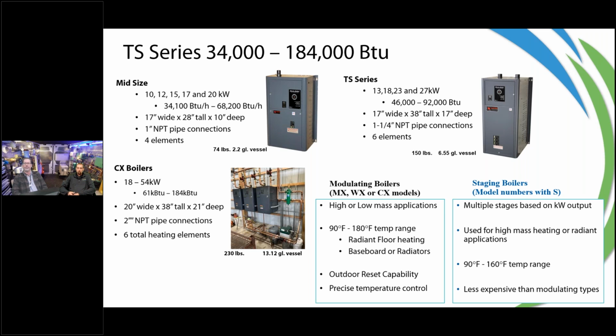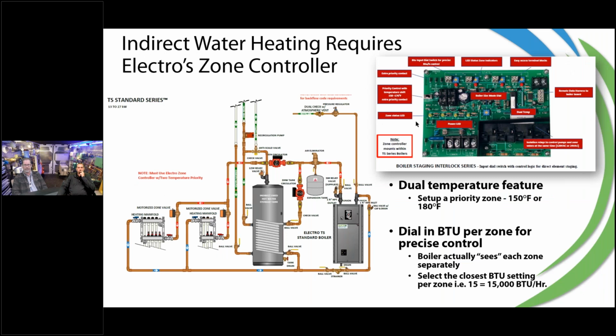We're big on air source as far as our product line with Fujitsu, but you have to be realistic. With refrigerant, you're going to run out of BTUs delivered, so what do you do for a backup? If they're friendly to the earth with PV, solar, and renewables in their home, that's how people were sold on a minus-15 heat pump being more than fine. But when it's 9 degrees out at night and you're not keeping up with the house, where do you go? Someone said to get rid of that fossil fuel, but now you have an option: you can trickle charge a little high temperature into existing hydronics in the house. Don't rip it out. Understand the power of keeping something, maybe leave the fossil fuel, or now I have this new thing called Electro, and I can bang off the solar panels to offset my monthly costs with the rebates.